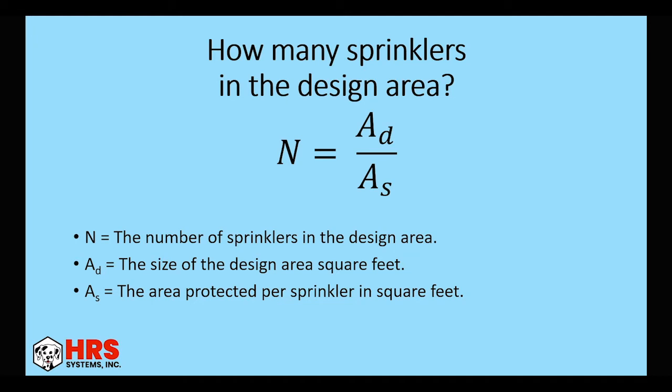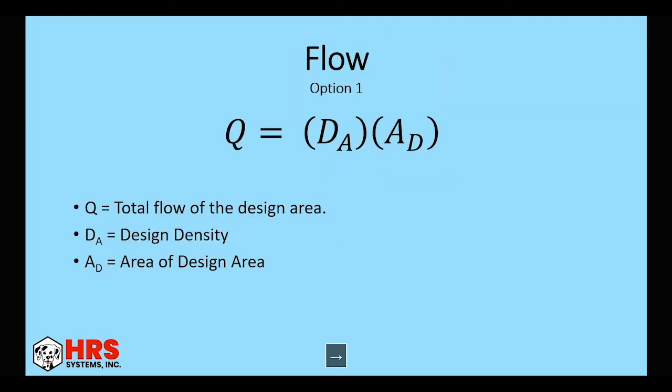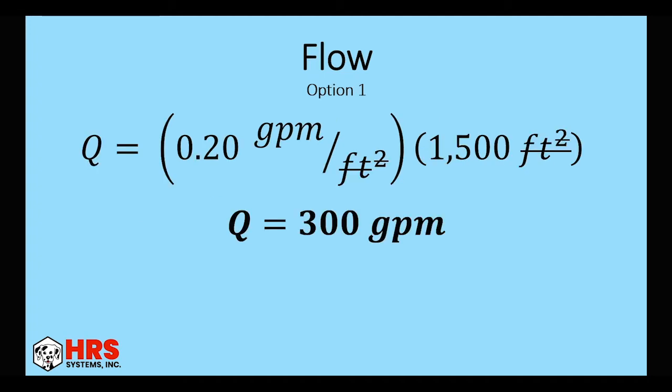So we quickly calculate how many sprinklers will be needed by taking the size of the design area over the protected area per sprinkler. So 1500 square feet divided by 120 square feet per sprinkler. That gives us 12.5 sprinklers or 13 sprinklers since you can't have half a sprinkler. Then we want to get the total flow for the design area. Again, we're not designing the system. We're just trying to figure out if we need a pump real quick. So we take our density over the coverage area. So 0.2 times 1500 square feet. That gives us a flow approximately of 300 GPM for the coverage area. Obviously, again, this is just an estimate.